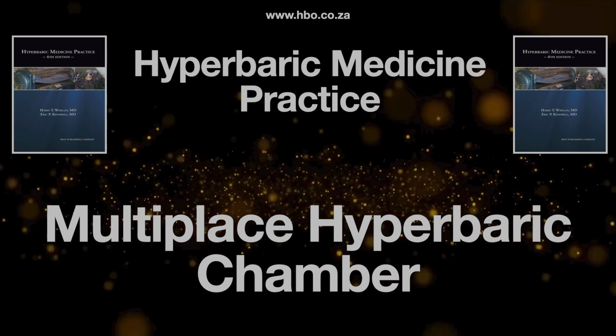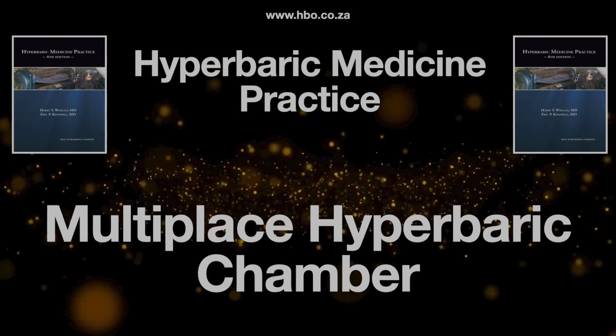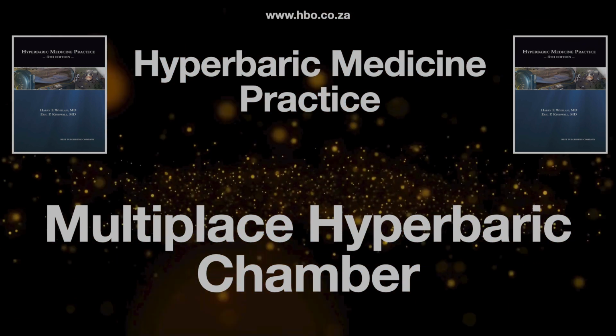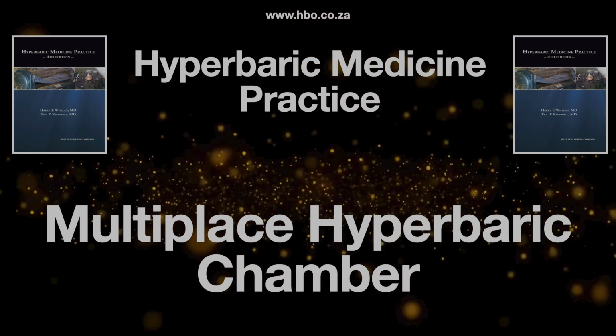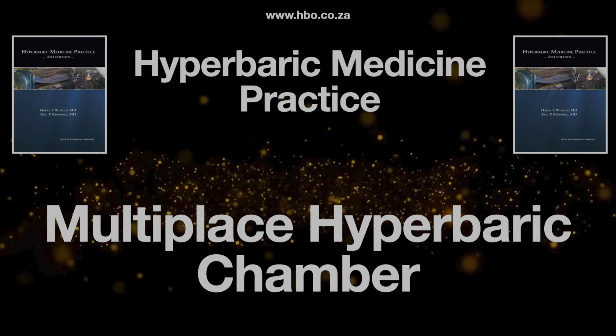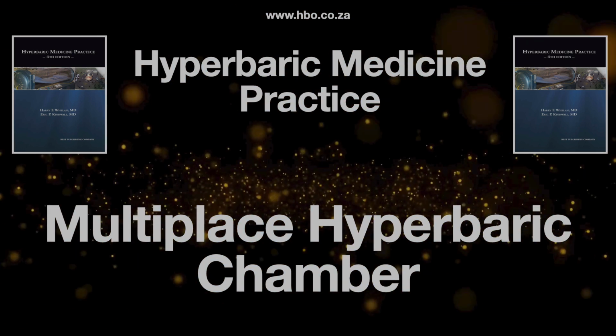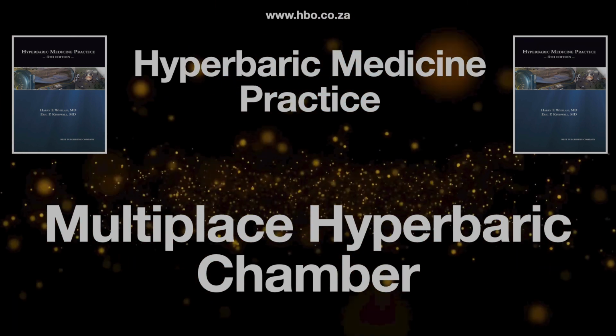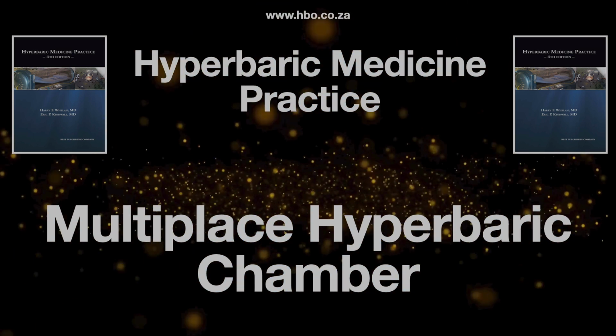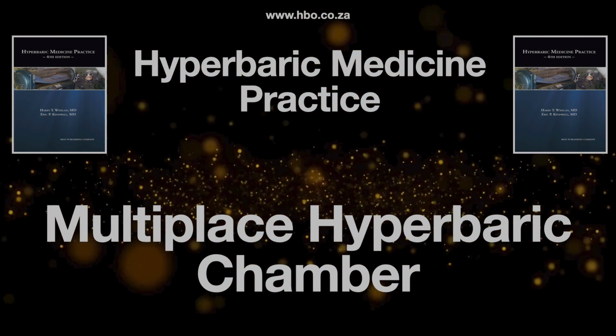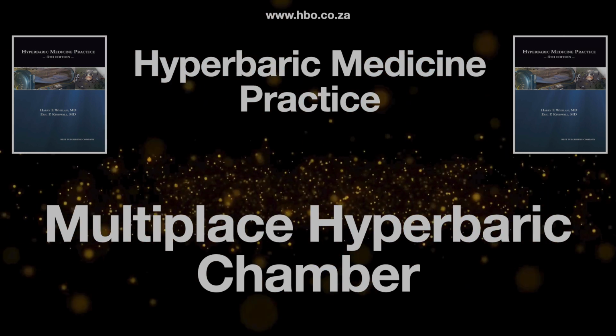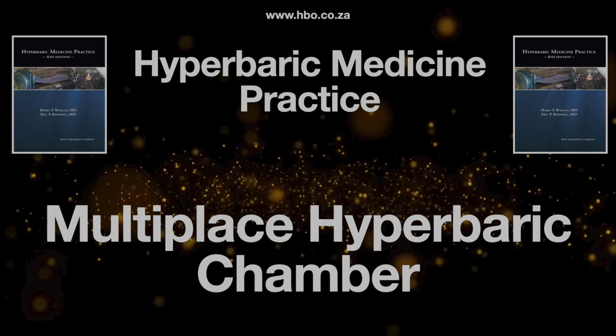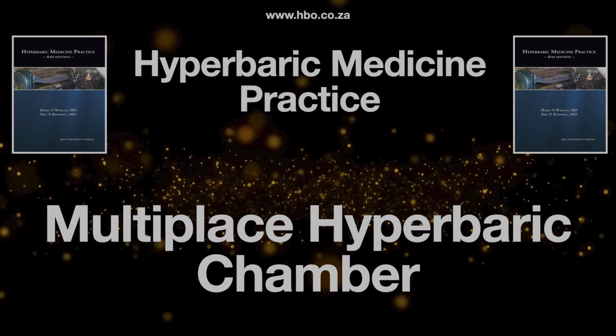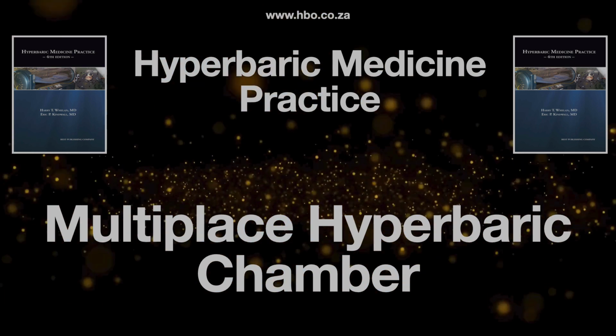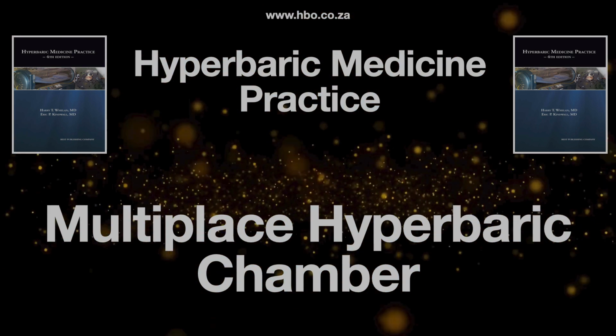A sprinkler system inside a sealed, pressurized room. That's hard to picture. It is a striking image, isn't it? But it's a critical safety component. It can be in the main chamber or the airlock or both, depending on the design. And it's not just like a regular office sprinkler, I assume. Not at all. It's a high-pressure deluge system. Uses compressed water, designed to dump a huge volume of water extremely fast. Needs to maintain pressure over 8.5 bar, deliver at least 50 liters per square meter per minute.